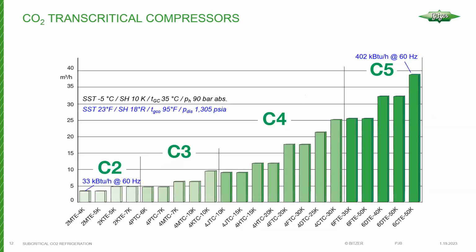Every once in a while it comes up, well, can I operate just outside that range? Whenever you have a question about the viability or acceptability of operating a compressor at a different speed range, these are the general speed ranges and we shouldn't go outside those limits. If there are special applications, never just try it. Always contact Bitzer for their advice on this.